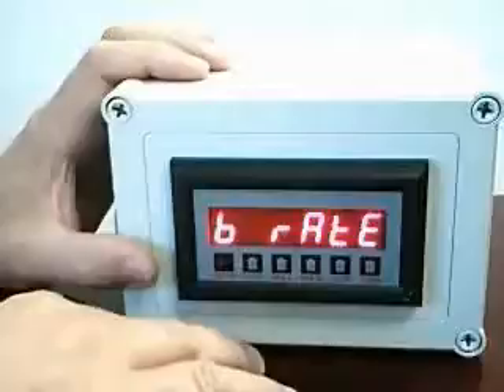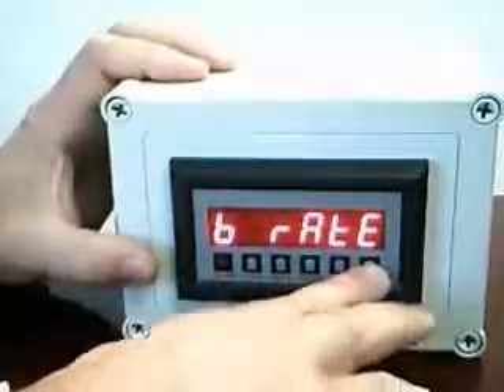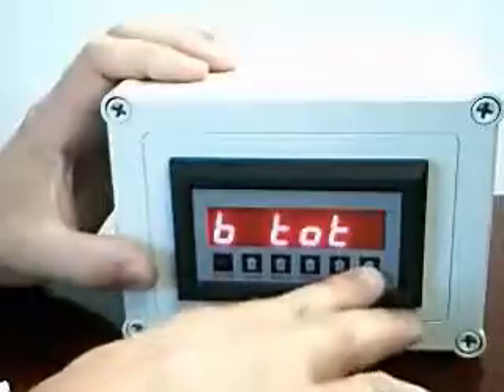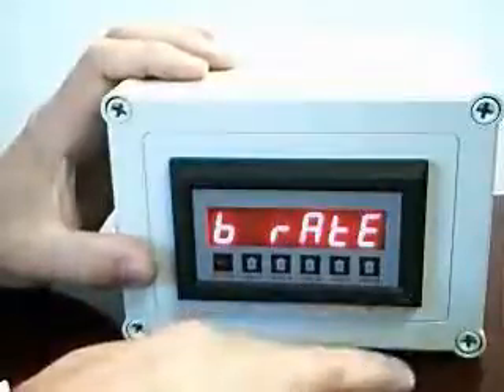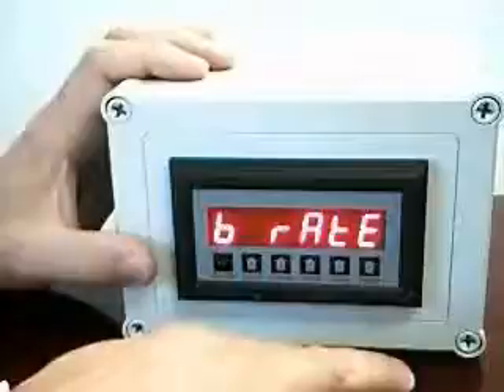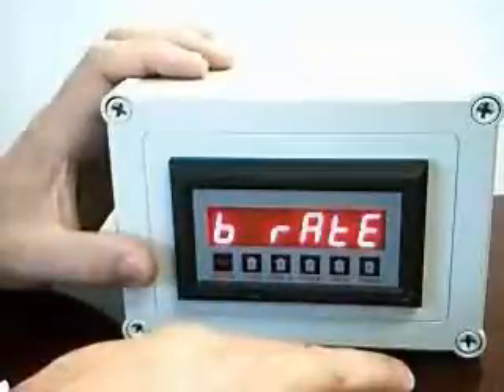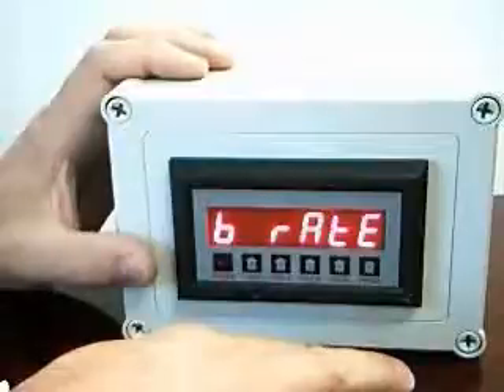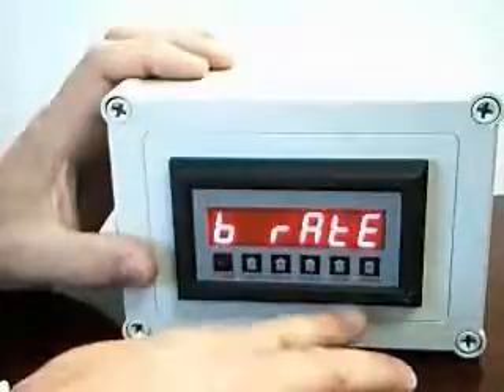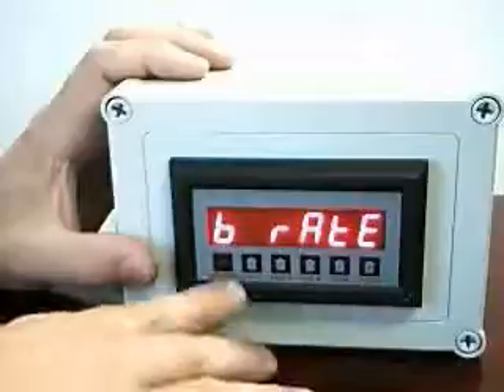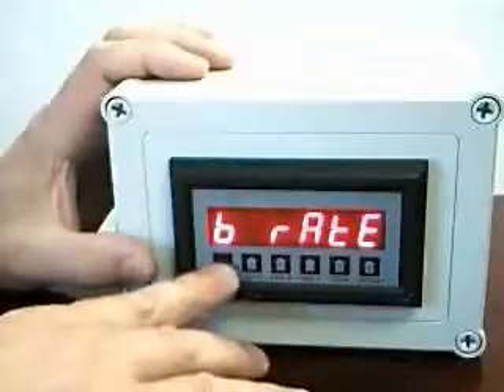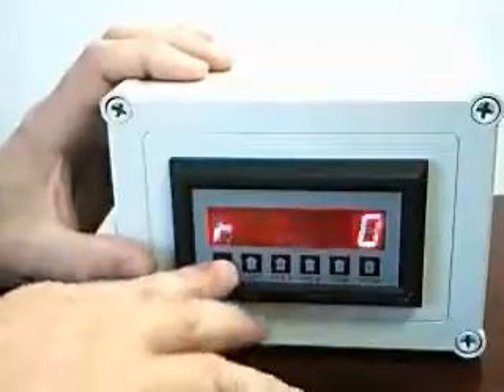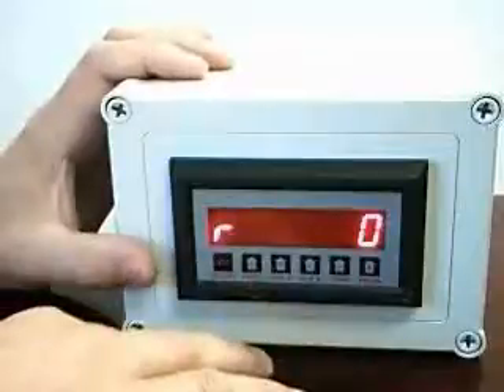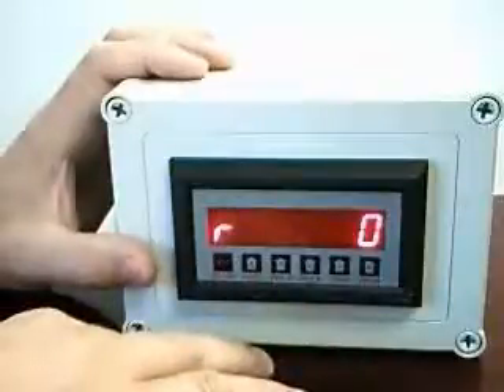This is similar in the sense that it again has selections of either total or rate. In some instances, you may wish to use the second totalizer as a low-speed scaled pulse output. The other modes are to assign it to rate, and that's what we're going to do in this application. We're back now in the run mode.